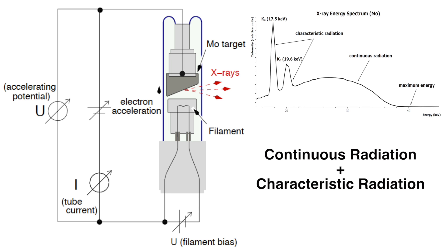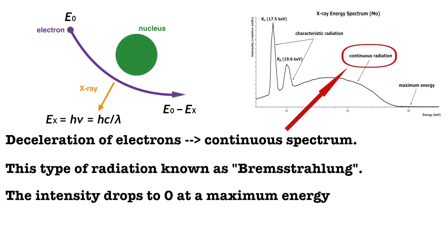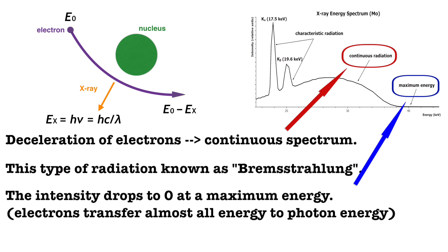X-ray output is plotted on graphs called spectra. An X-ray spectrum is continuous, and the intensity reaches zero at a certain maximum energy point. In addition to the continuous spectrum, depending on the accelerating potential, there may be discrete features superimposed on the spectrum. The continuous spectrum is due to deceleration of electrons hitting the target. This type of radiation is known as Bremsstrahlung. The intensity drops to zero at a certain maximum energy or minimum wavelength when electrons transfer almost all energy to photon energy.